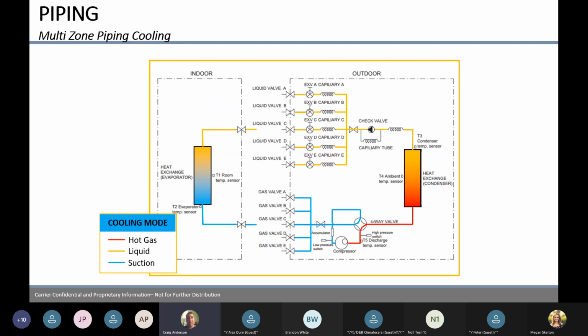Now, once we get into a multi-zone, similar, the way the gas is going to flow, the four-way valve is in cooling, so it's not energized. And then you'll notice all the EEV valves. So each circuit has its own valve that's going to monitor what that indoor unit is doing. And then when we go into heating mode, everything is going to change. It's going to switch around.